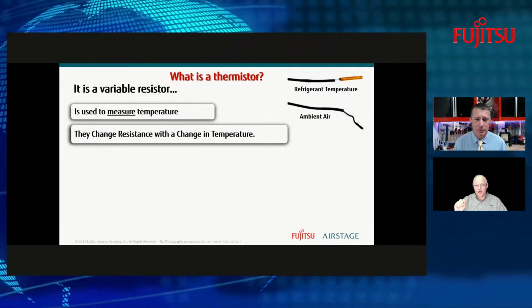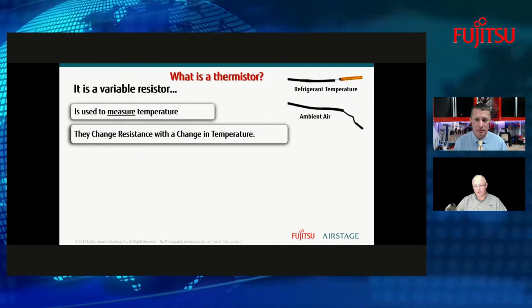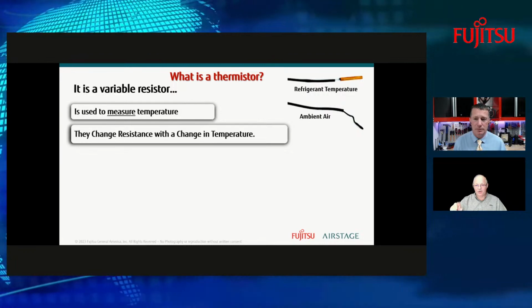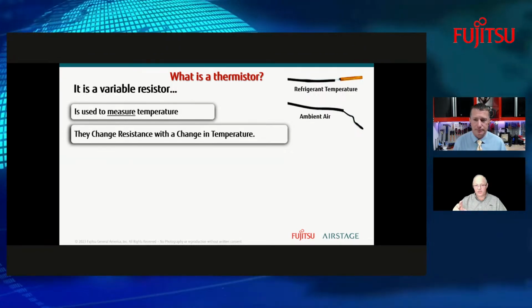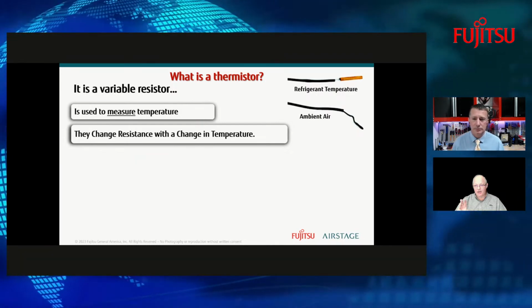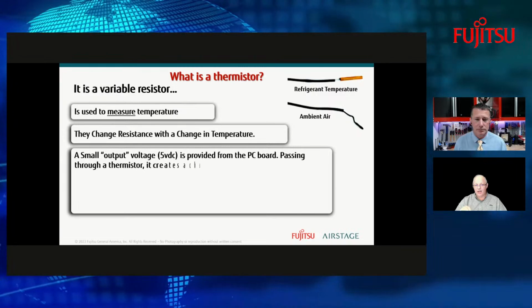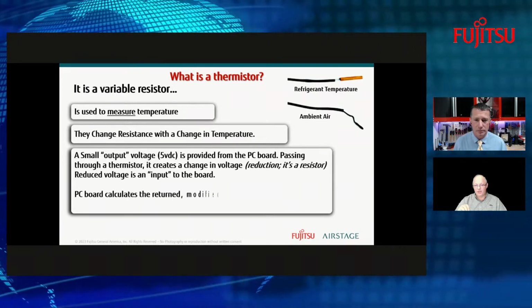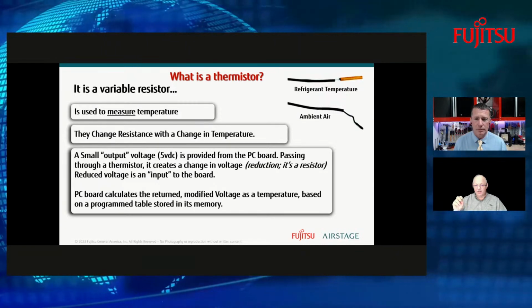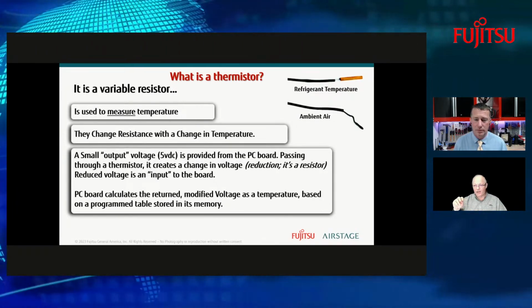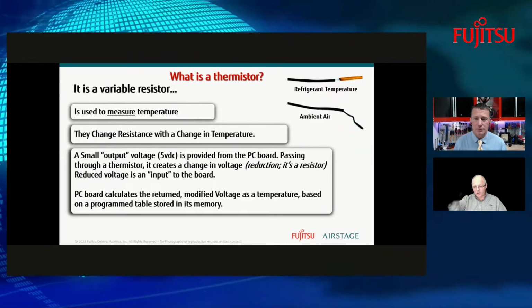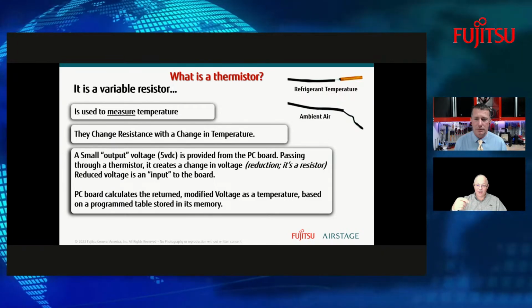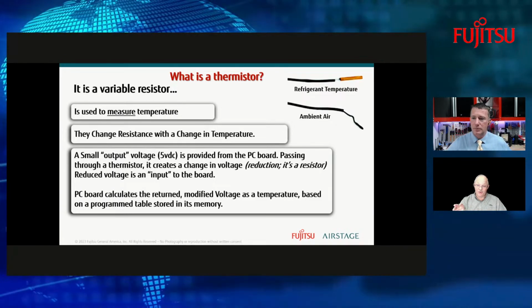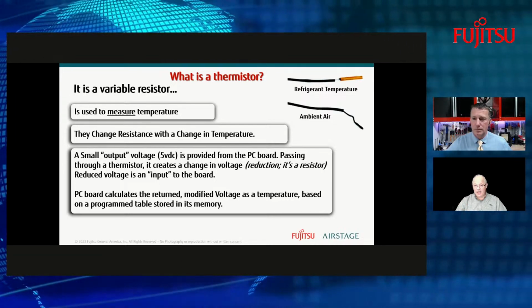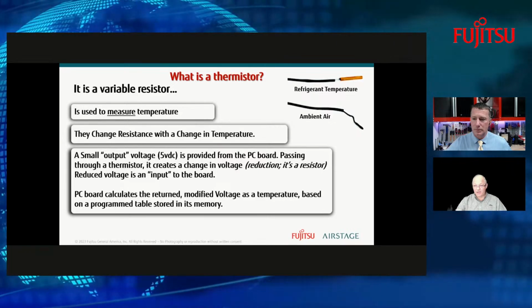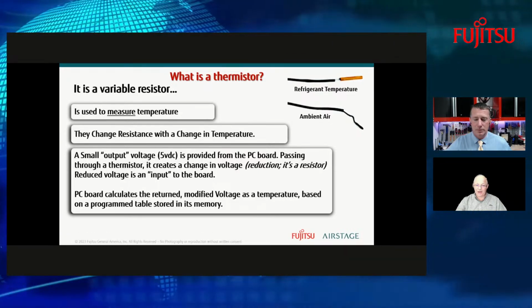So it's looking at a change of resistance with a change in temperature. As the temperature goes up, resistance is going to go down, and vice versa. As that temperature is changing, we're going to get a small output voltage that's going to be provided to the PC board. This 5 volts DC is going to come out of the board and go into the thermistor. It's going to route through the thermistor and back out. Because there is resistance in the thermistor, there's going to be a drop in voltage. So it's that reduced voltage coming out of these thermistors that's actually the input information back to the board.